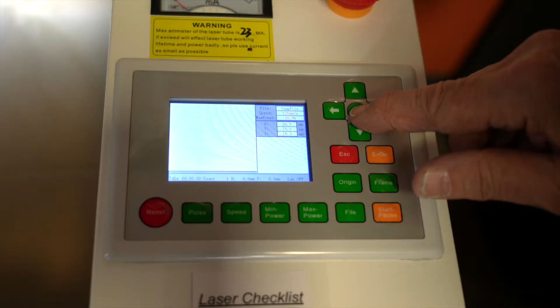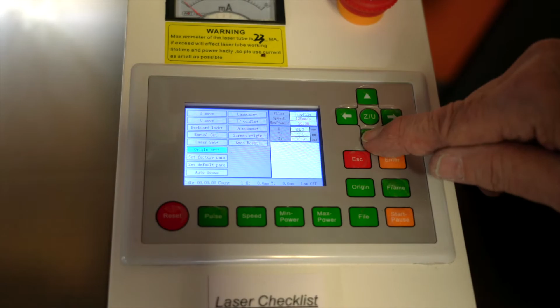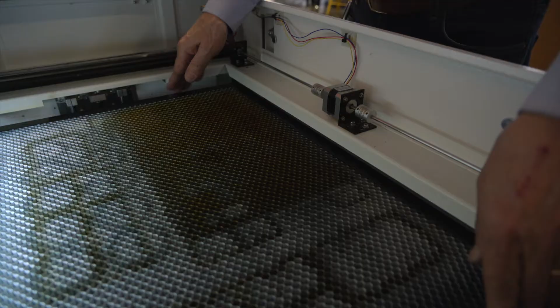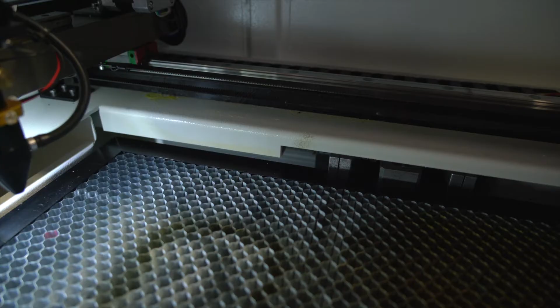When you press the Z/U button, you will see a menu of functions. Use the left and right arrow to move the honeycomb bed up and down. Note that the honeycomb bed clears the edges of the surrounding cabinet by less than an inch on all sides. Be sure to position the honeycomb bed in the center of the platform on which it sets. If it is offset to any side, it will interrupt the motion of the platform.